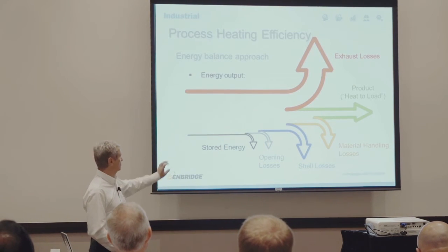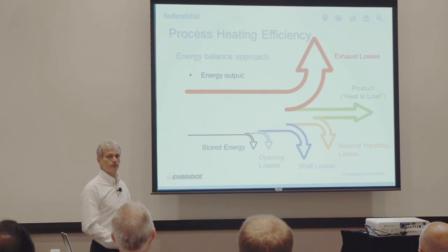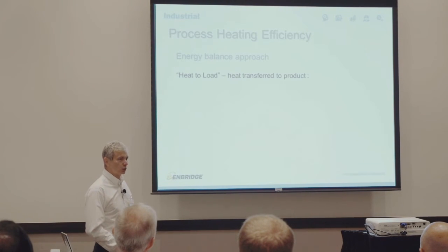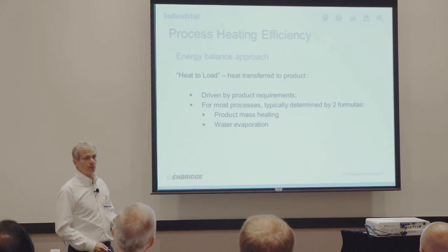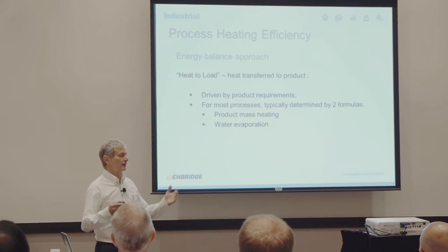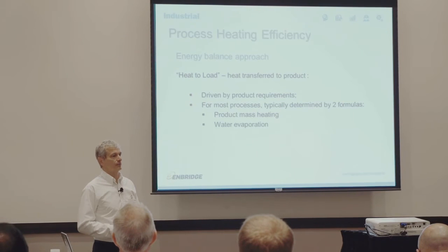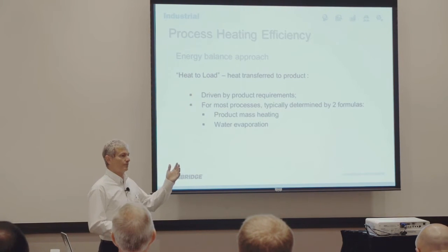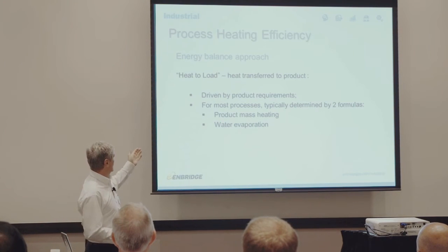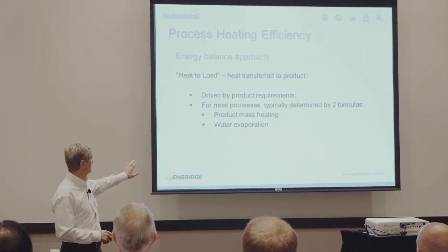So once you start looking at process heating efficiency this way, you can see all sorts of opportunities to increase efficiency without actually touching the process itself. The heat to load is driven by product requirements. If you have a powder coat paint line, the part must reach about 370–380°F for a certain duration. If you have to dry a product from 80% to 10% moisture, you must evaporate a certain amount of water — that energy is the heat load. For most processes this is determined by the two formulas: product mass heating and water evaporation.